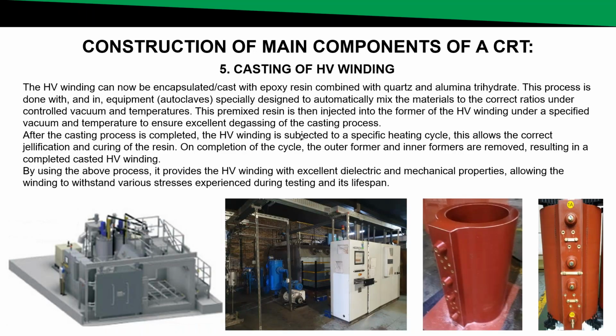So now let's have a quick look at the actual casting of the HV winding. Once the jacket pre-casting process has been completed, the HV winding can now be encapsulated, casted with epoxy resin combined with quartz and alumina trihydrate. This process is done in equipment, typically autoclaves, specially designed to automatically mix the materials to the correct ratios under controlled vacuum and temperatures. This pre-mixed resin is then injected into the former for the high voltage winding under a specified vacuum and temperature to ensure excellent degassing of the casting process.